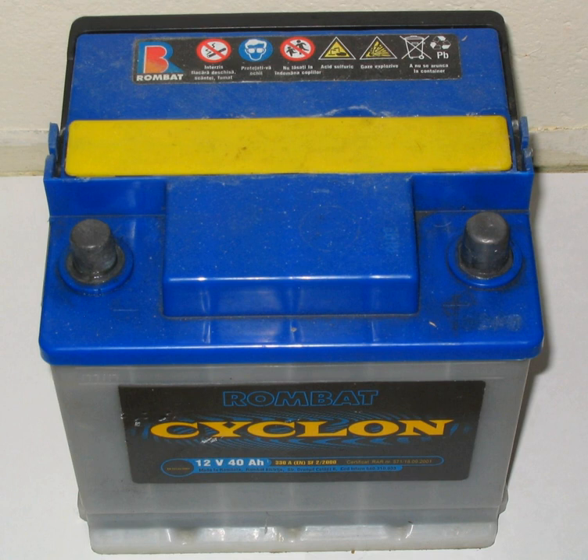Sulfation can be avoided if the battery is fully recharged immediately after a discharge cycle. There are no known, independently verified ways to reverse sulfation. There are commercial products claiming to achieve desulfation through techniques such as pulse charging, but there are no peer-reviewed publications verifying their claims. Sulfation prevention remains the best course of action, by periodically fully charging the lead-acid batteries.